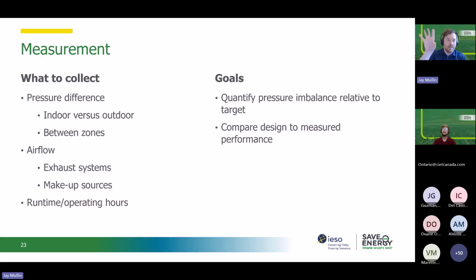So all the stuff you got on that bench evaluation or the desk evaluation up front, all the nameplate stuff, the facility schematics, how does that compare to actual performance and actual operations? So you have the nameplate values, you have those layouts. Do they match up? There's often, someone moved a duct to serve a new piece of equipment, and that wasn't reflected in the site drawings. So the whole makeup air sources have shifted over time. So you want to do that verification of, does the measured data align with assumptions around how things are running?